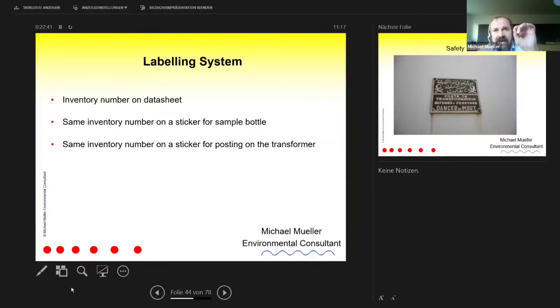You know, the samplers are not stupid. They may be low level, but they are not stupid. They could go to one transformer and fill 10 bottles, then go back and have a nice day. No. To ensure that they go to each transformer, they must put a sticker with the inventory number on the transformer, so they are forced to go to each transformer and take a sample.